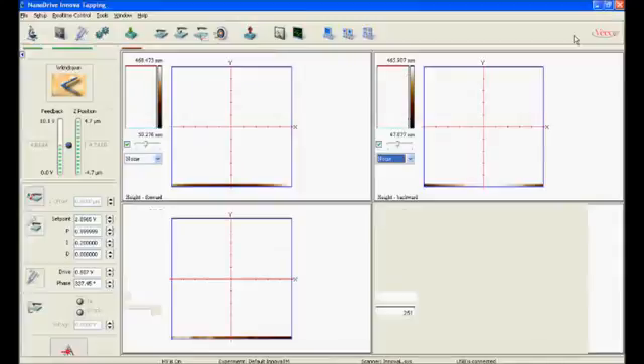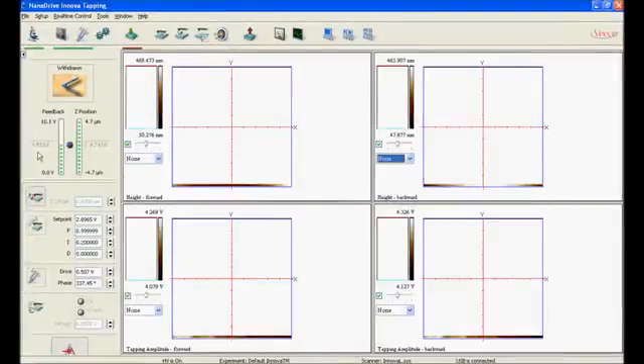We will now approach the surface properly. Note the feedback value, shown here at roughly 4.8 volts. Adjust the set point to roughly 3/4 of this value, or simply 1 volt less. Remember to always hit Enter for the program to accept your changes. We have now clicked the Approach button, and we wait for the tip to engage.